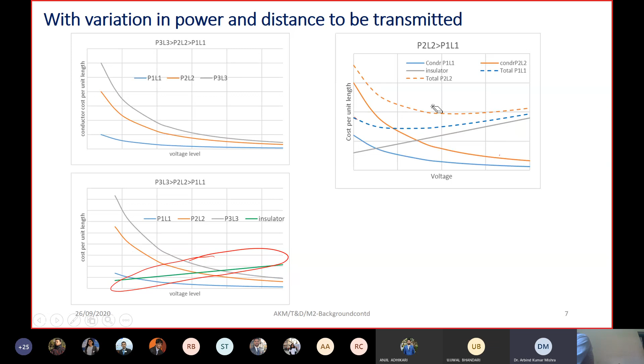So the total cost for the conductor plus the insulator in case of P1 L1 is represented by this blue dotted line, and the total cost for conductor and insulator in case of P2 L2 is represented by this orange dotted line. As you can see, the most economical voltage is changing. For P1 L1 case, the most economical voltage is somewhere here.